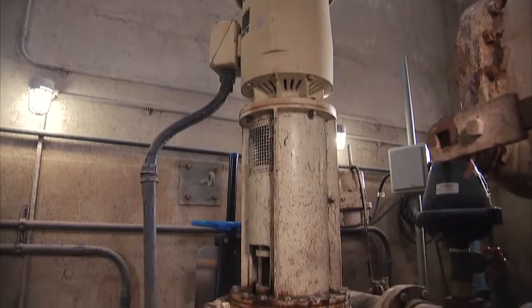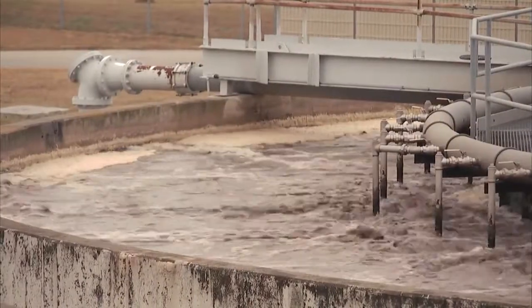The Municipal Utility District lift station, located in suburban Houston, suffered from nearly weekly pump clogs. The main reason our lift pumps are clogging is due to ragging, which basically happens when people flush things down the toilet that they shouldn't.